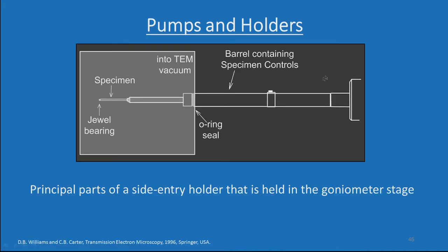Coming to the holders — this is how a TEM holder looks like. There is a barrel containing specimen controls, an o-ring seal, and the shaded section is under vacuum while the other part is not. The specimen sits inside, and there is a bearing which senses the position of the specimen inside the column. This is a side entry holder held in a goniometer stage.